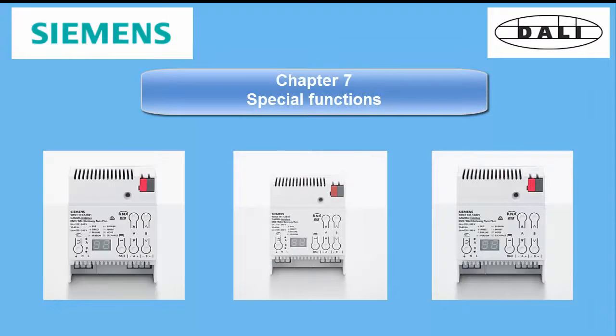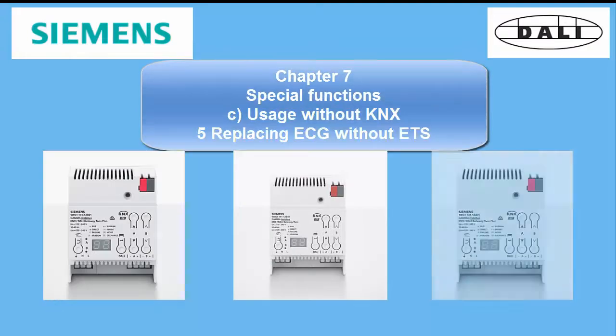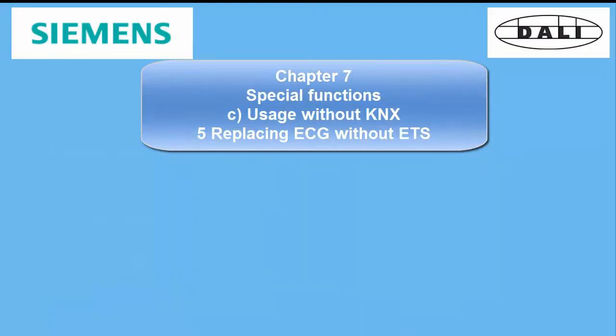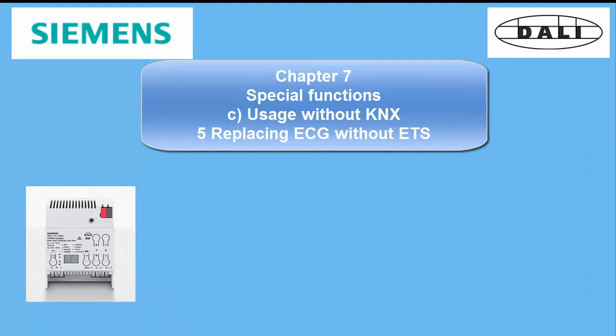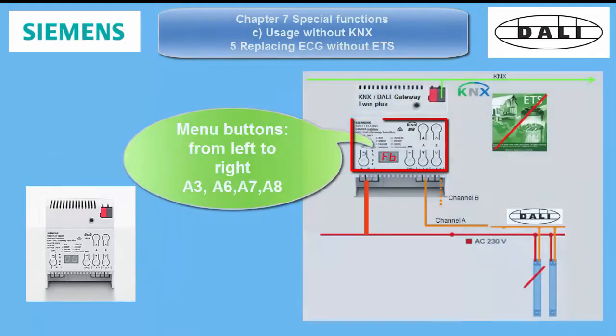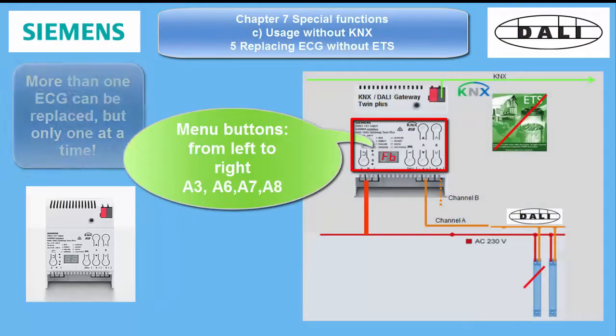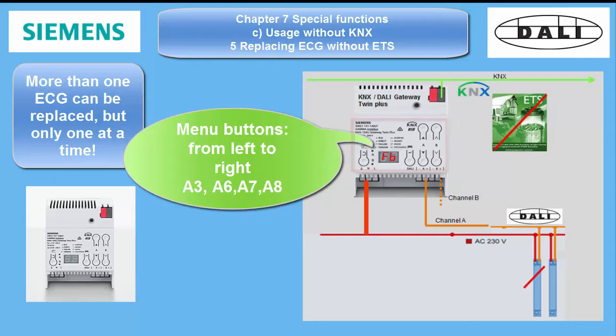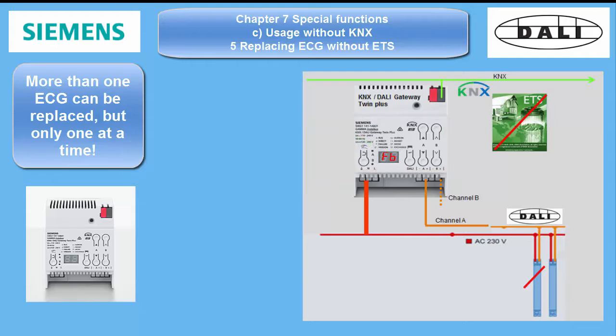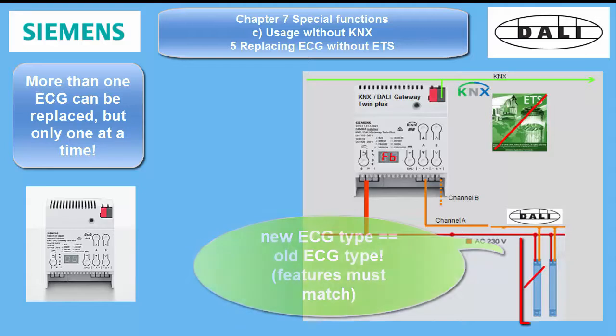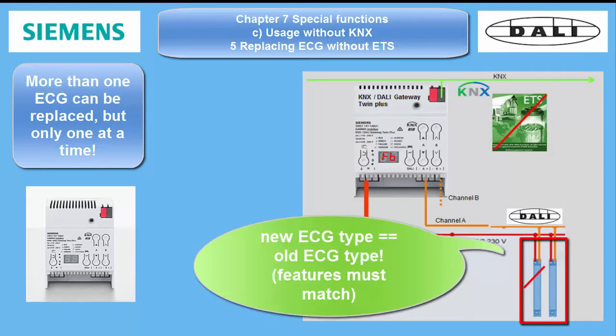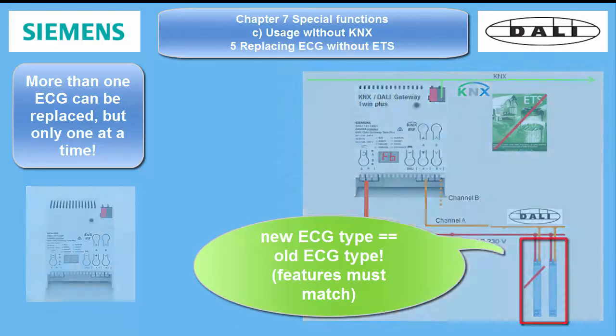Replacing ECG without ETS. The gateway supports this mode when the front side menu buttons are pressed according to the BMA to get into the replacement mode. You can replace more than one defective ECG, but only one at a time. You have to make sure that the replacement device is identical with the defective ECG. Please see BMA how to do it.